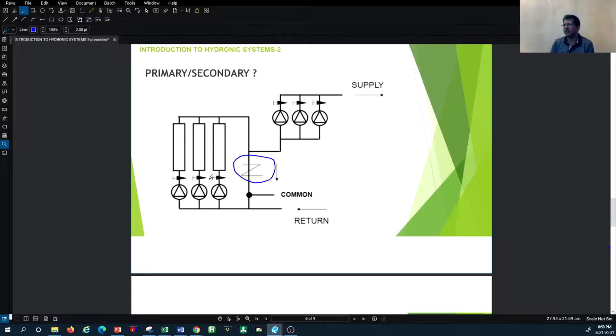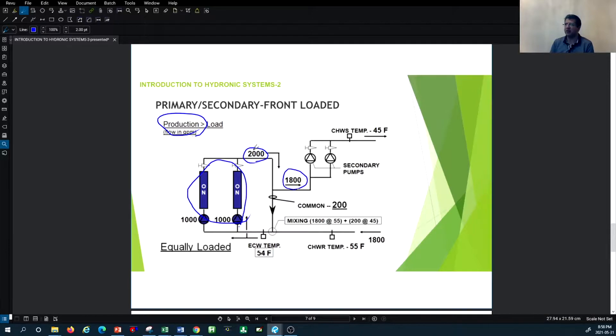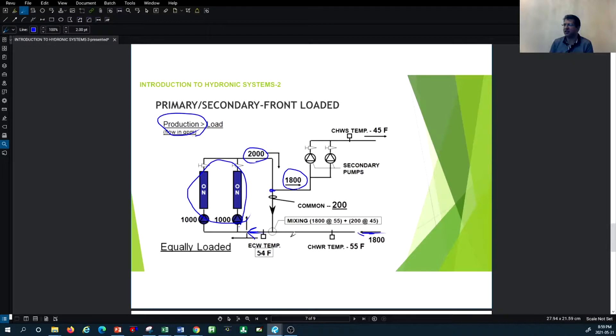In the third scenario, production is higher than load. Each chiller has 1000 GPM capacity, so together they recirculate 2000 GPM. If the secondary loop only requires 1800 GPM, then 2000 GPM arrives at the common pipe, 1800 goes to the secondary loop for the building load, and 200 GPM is recirculated back to the primary loop. On the return side, 1800 GPM comes back and is added to the 200 GPM, giving 2000 GPM returning to the primary loop.